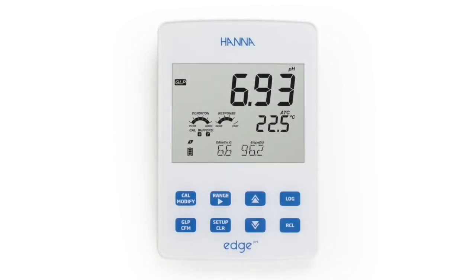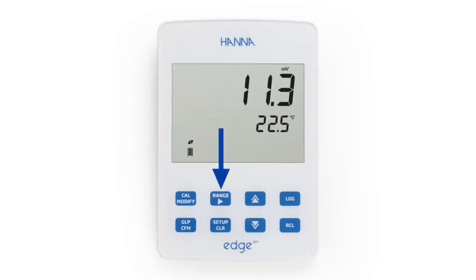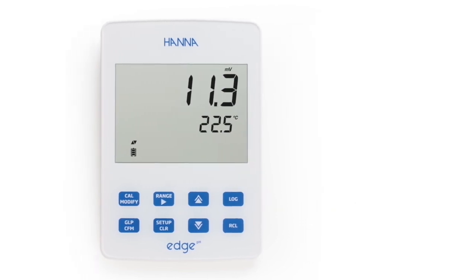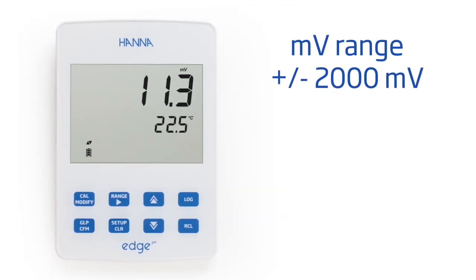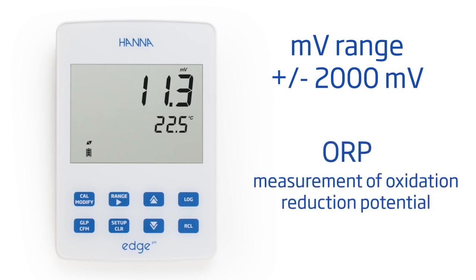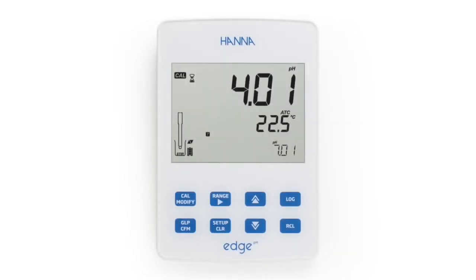Switching between pH and millivolt mode is made easy by simply pressing the range button while in measurement mode. The millivolt mode has an expanded range for the measurement of oxidation reduction potential with an optional ORP electrode. Pressing the dedicated Cal button allows users to enter automatic calibration.